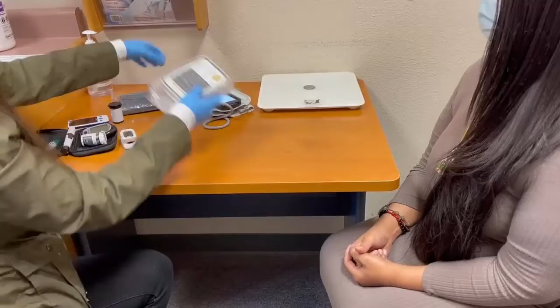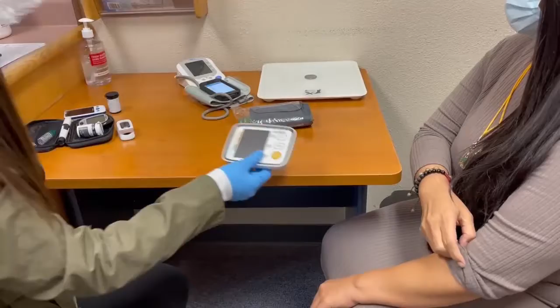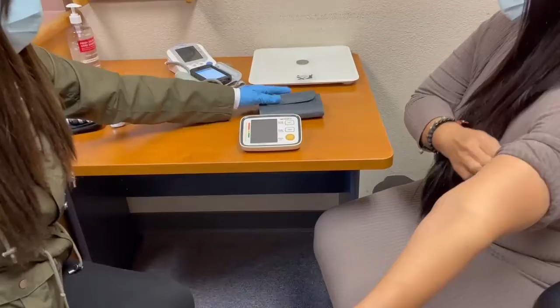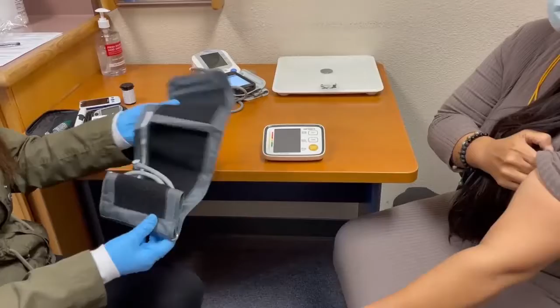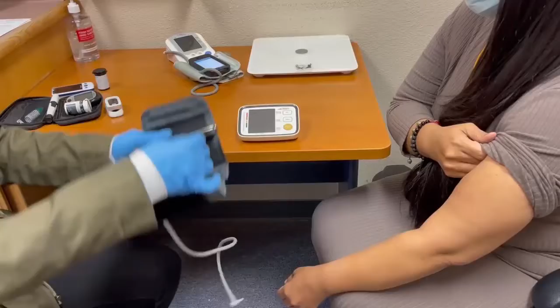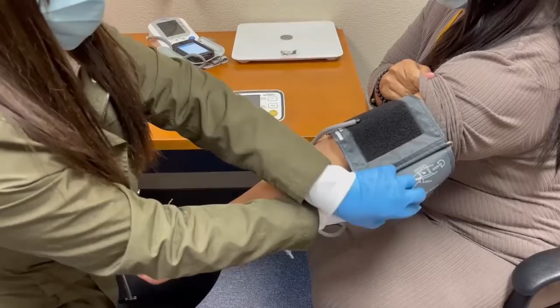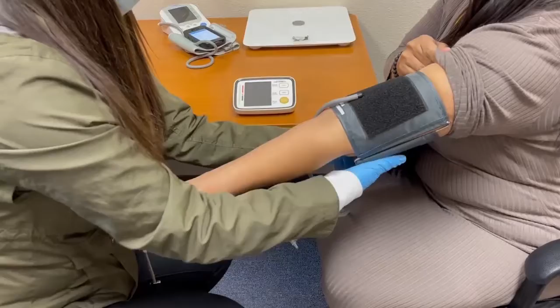Now, we are going to take a reading using the cellular blood pressure monitor. When taking a reading, the connector must be aligned to your hands. The reading will take some time to finish, so relax your arm, and your hands must be on a table. The device will take a reading. After the reading is completed, please do not turn off the device, as it will upload the data through the cellular network. This device has a SIM card inside. The device will turn off by itself after it has uploaded the data. The same works for the cellular scale, glucometer, and pulse oximeter. If you encounter any issue, or data is not going through, please contact our customer support.